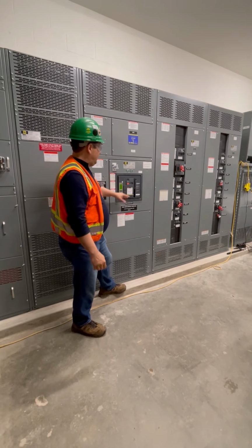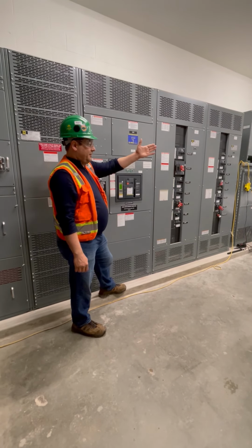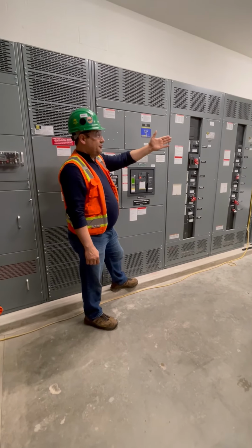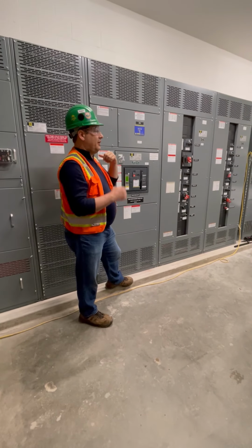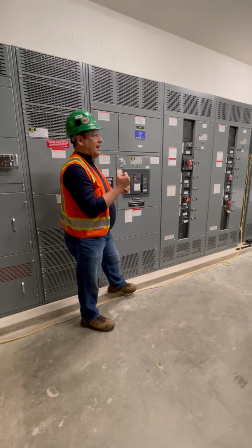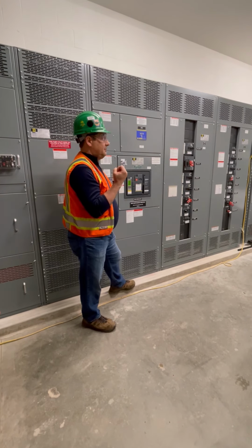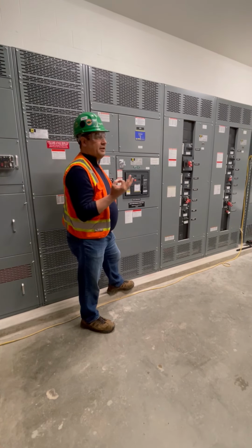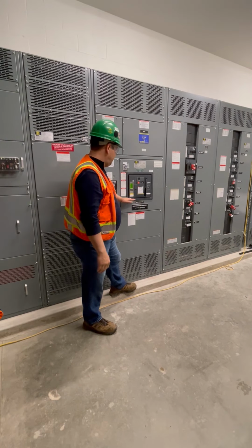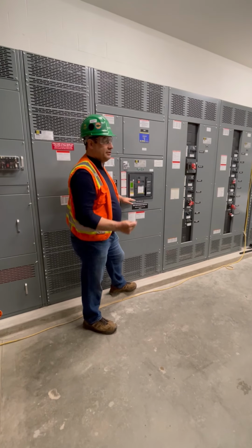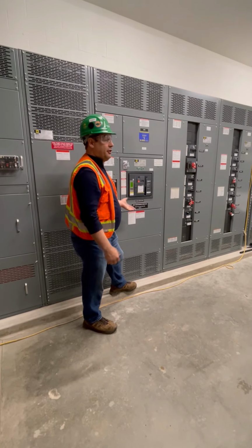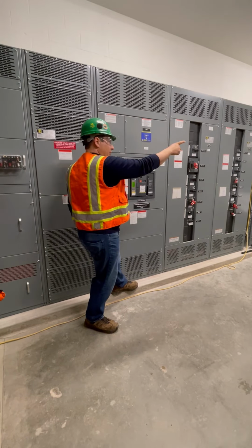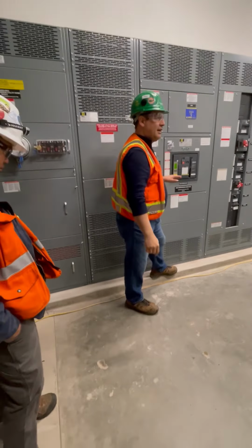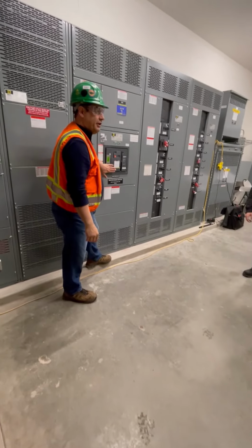Now, the breakers downstream, let's say you have 40 amp, 50 amp breakers downstream, thermomagnetics, they have a very long timing. Sometimes they can count for like 10 seconds before it trips. This one reaches that level, it's pretty quick. So it could be that you have a ground fault way downstream, created enough of a magnitude of a fault to trip this breaker, right?